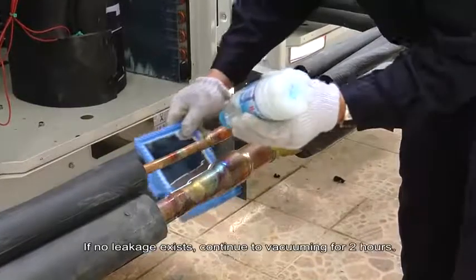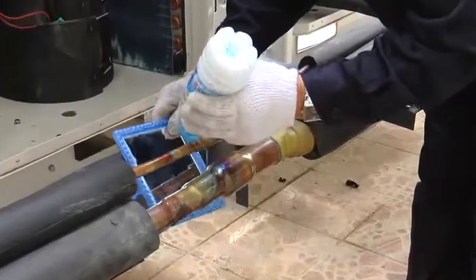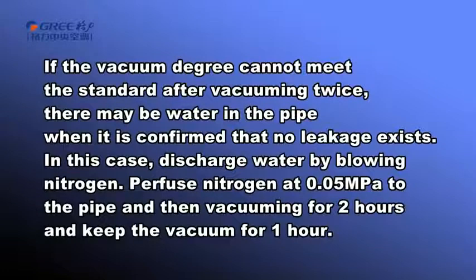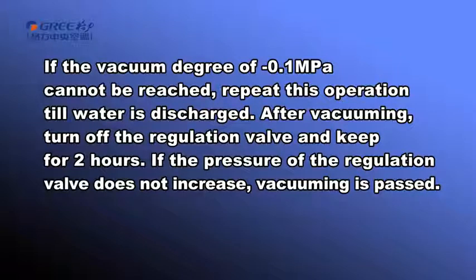If no leakage exists, continue to vacuum for 2 hours. If the vacuum degree cannot meet the standard after vacuuming twice, there may be water in the pipe when it is confirmed that no leakage exists. In this case, discharge water by blowing nitrogen. Perfuse nitrogen at 0.05 megapascal to the pipe, and then vacuum for 2 hours and keep the vacuum for 1 hour. If the vacuum degree of minus 0.1 megapascal cannot be reached, repeat this operation till water is discharged. After vacuuming, turn off the regulation valve and keep for 2 hours. If the pressure of the regulation valve does not increase, vacuum is passed.